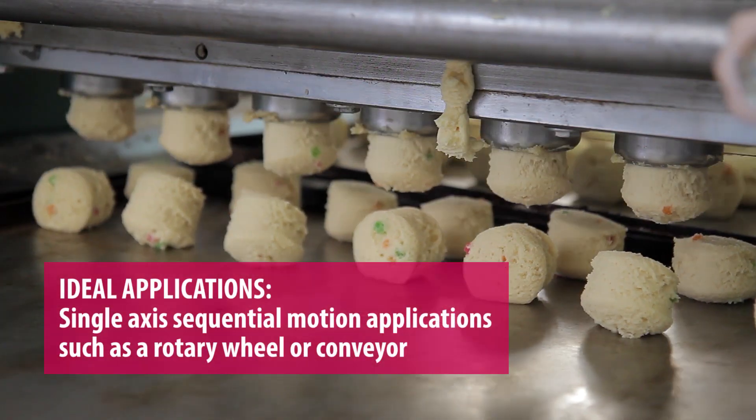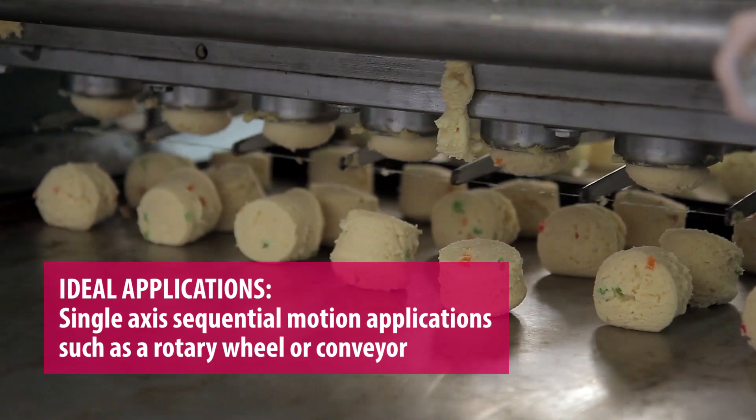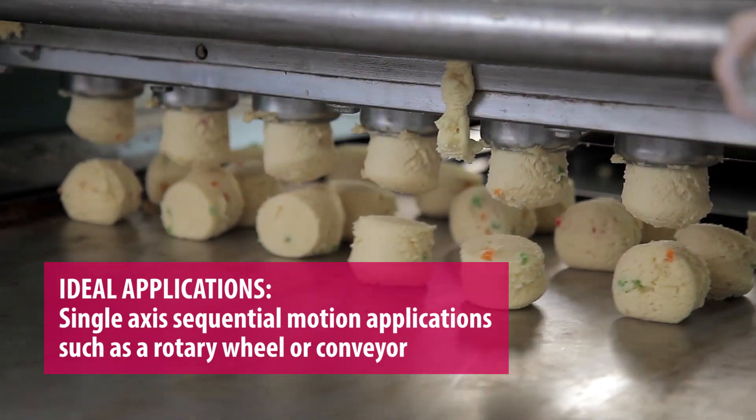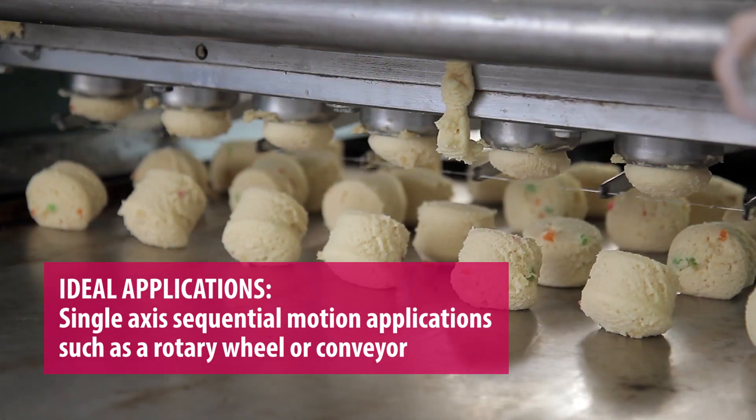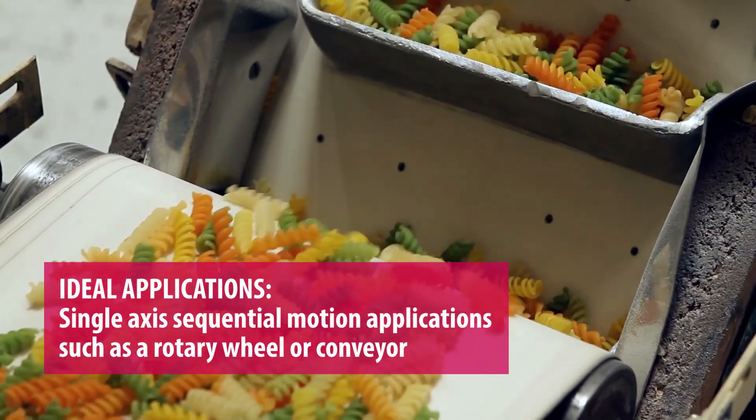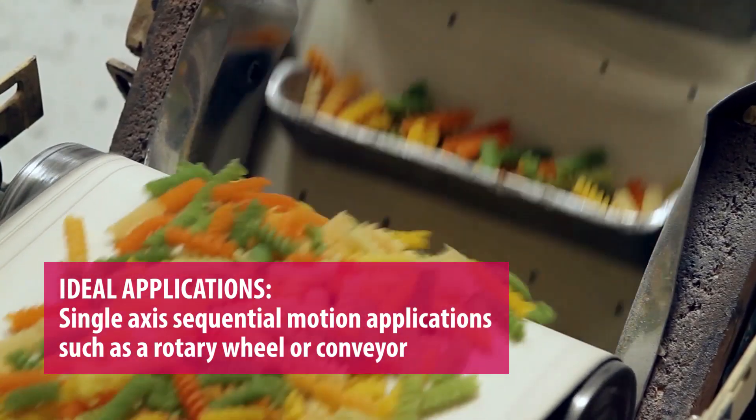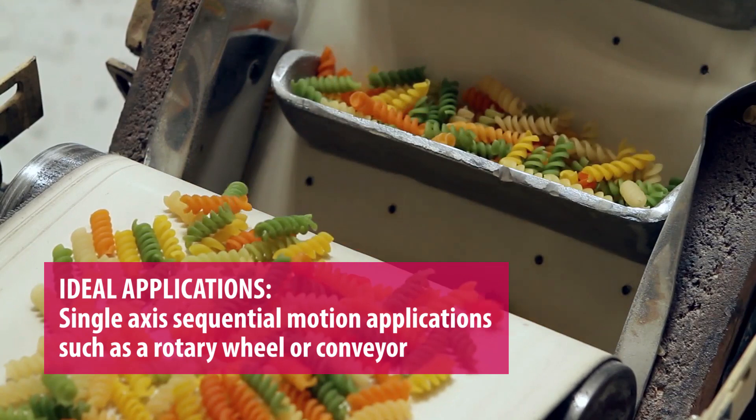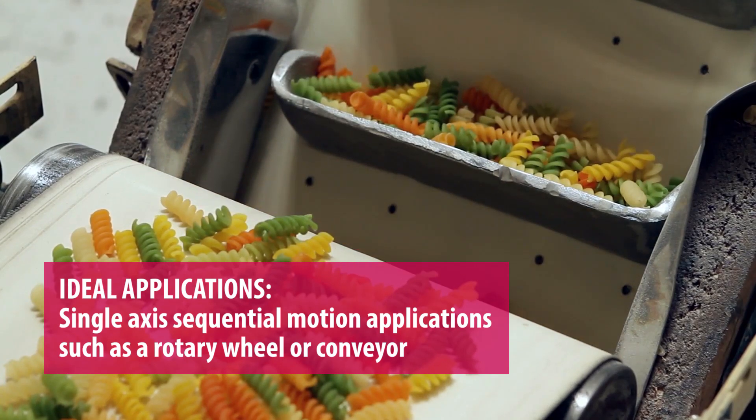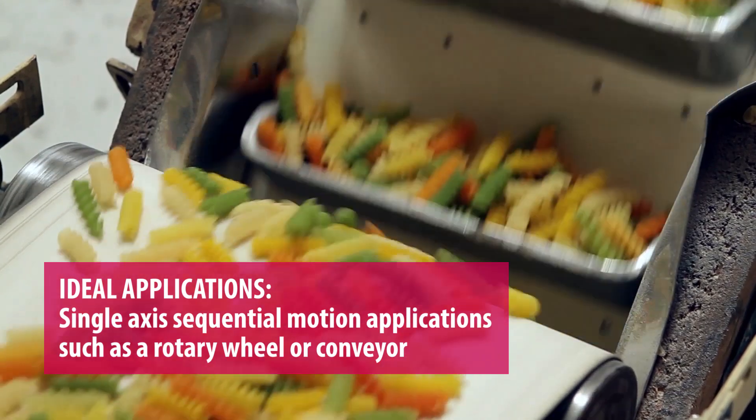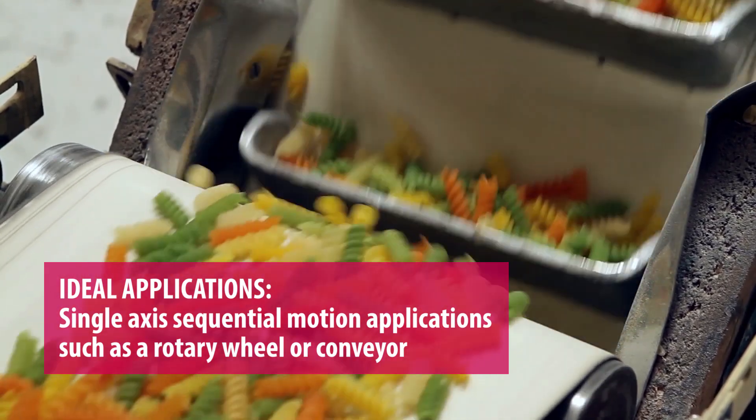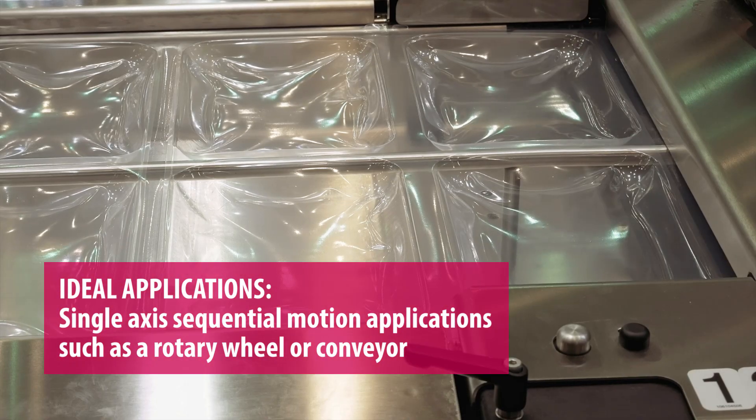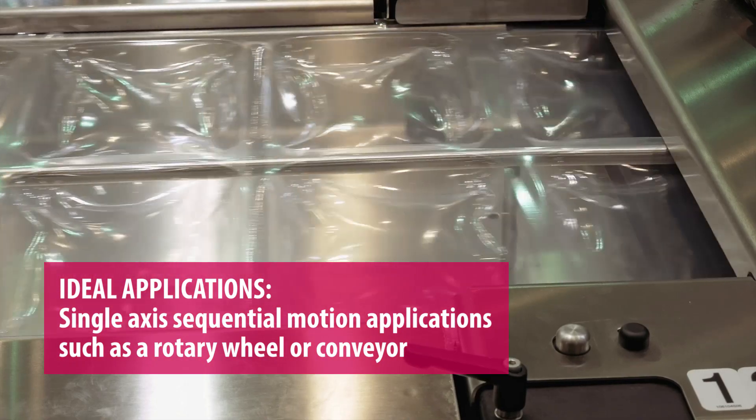So what are some applications where this would be beneficial? Yeah Jake, so this internal positioning module would really be best suited for applications with single axis motion or sequential motion such as a rotary wheel or a conveyor. Applications that require complex coordinated motion or multi-axis motion would really be best suited to be driven with a PLC or a motion controller.